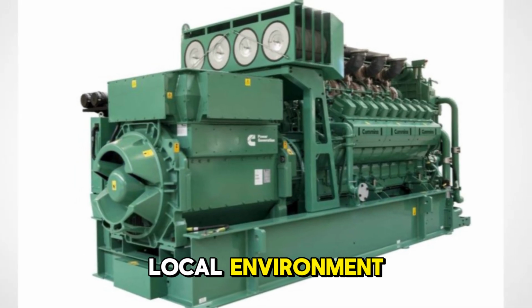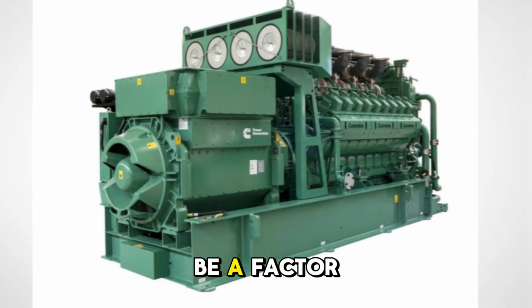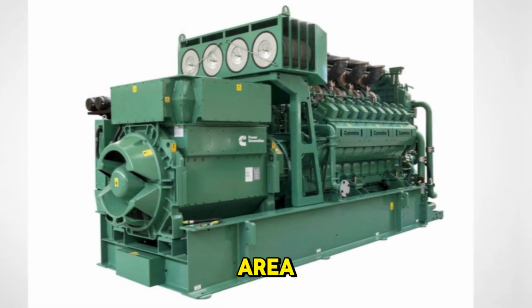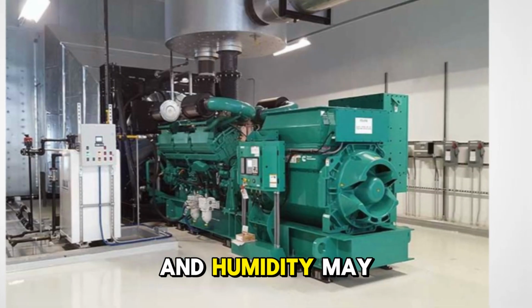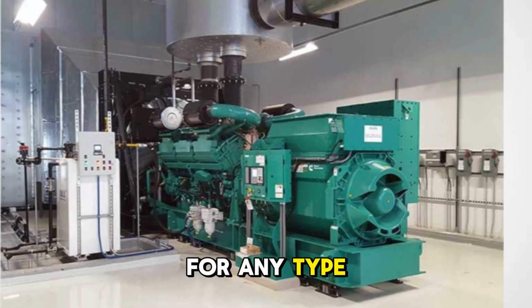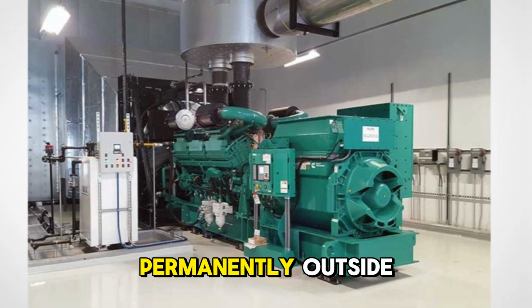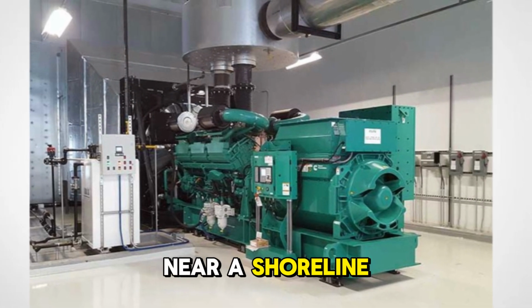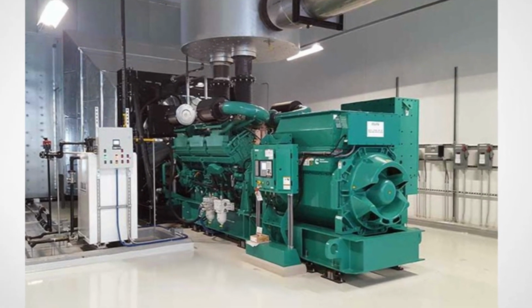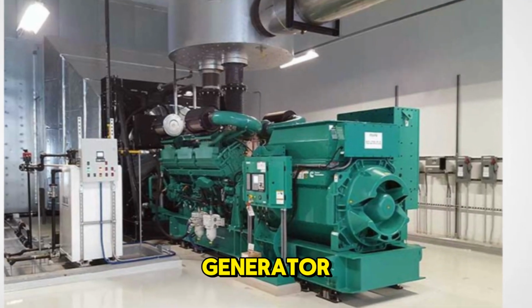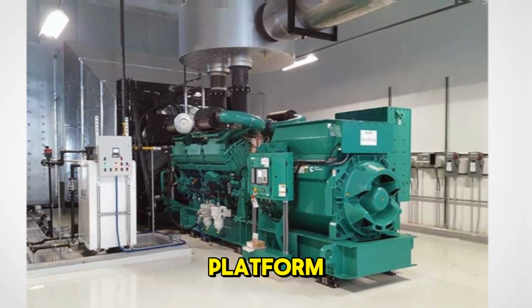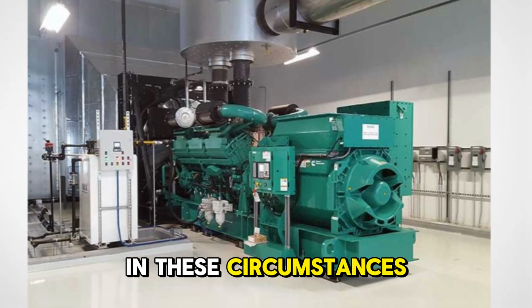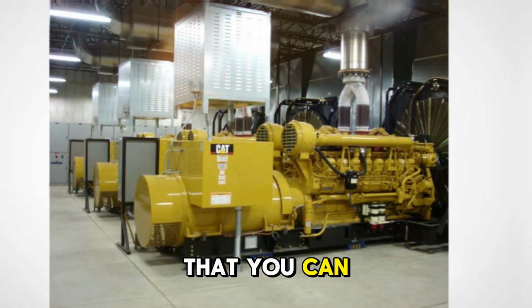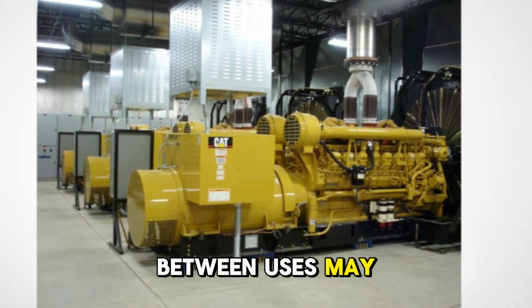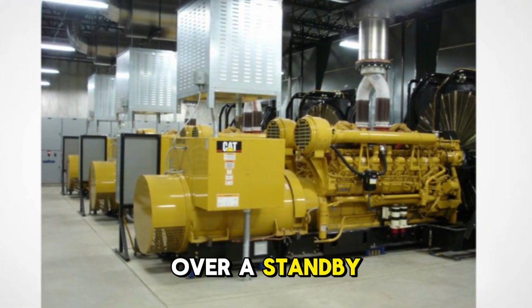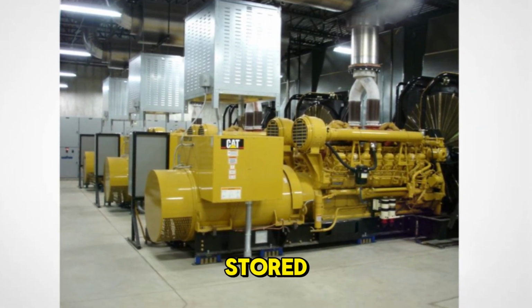Local environment may also be a factor. If you live in a coastal area, salty sea air and humidity may create more wear and tear for any metal machinery installed permanently outside. If you live near a shoreline where flooding is a concern, extra steps like installing it on a raised platform may be necessary. In these circumstances, a portable generator you can keep out of harm's way between uses may carry a significant advantage over a standby generator that can't be moved or stored.